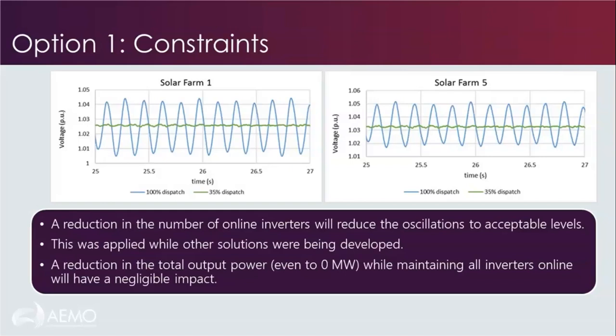An important finding here, which I shared the underlying theory of at the ESIC fall workshop, so I'm not going to discuss it in great detail now, is that we weren't able to achieve the same performance, or anywhere near it, by solely reducing the total output power of the inverter-based generator. An extreme that we tried was to reduce the total output power to zero while maintaining all inverter-based generators, and we would see almost the same level of oscillations as corresponds to the 100% dispatch case that is shown here.